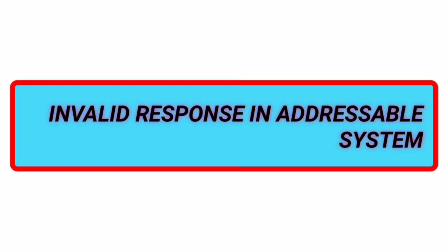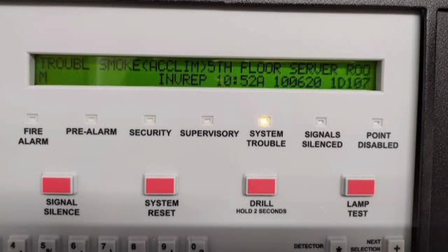I will go deeper into classes of wiring in an upcoming video. NAC devices like bells, horns, strobes, and visual notification appliances get open trouble shown as a NAC fault or trouble on the NAC circuit. To clear this open trouble, we go with the same troubleshooting approach as the conventional type open fault.